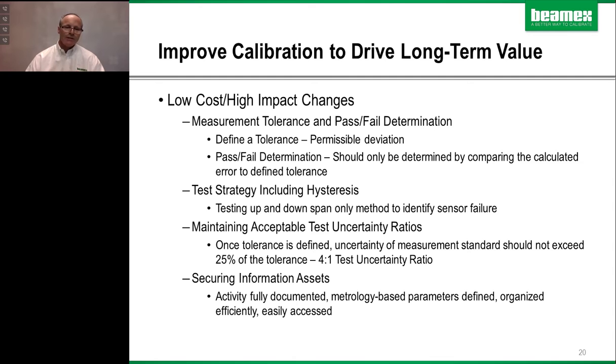Every instrument needs to have a tolerance or an error budget. Please don't base this on the accuracy stated by the manufacturer of the instrument. It should be a combination of what the process requires, the criticality of the instrument, and the environment that it's used in, to define a tolerance for each instrument. It's okay to have an overall tolerance, but each instrument needs to be looked at. The second part of that is being able to determine the uncertainty. Tolerance is required in order to develop an uncertainty budget as well.